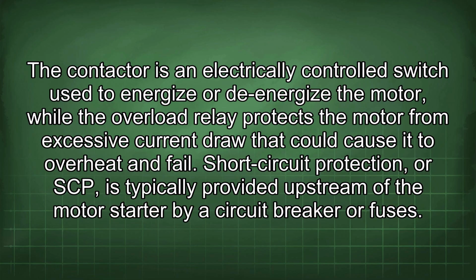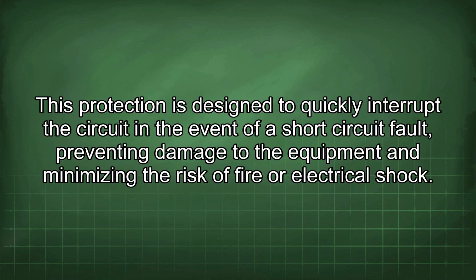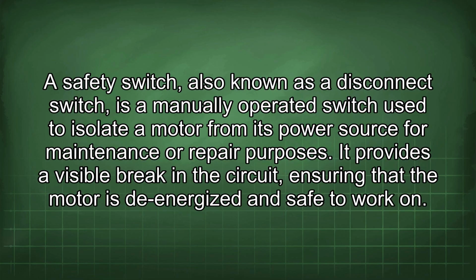Short circuit protection, or SCP, is typically provided upstream of the motor starter by a circuit breaker or fuses. This protection is designed to quickly interrupt the circuit in the event of a short circuit fault, preventing damage to the equipment and minimizing the risk of fire or electrical shock. A safety switch, also known as a disconnect switch, is a manually operated switch used to isolate a motor from its power source for maintenance or repair purposes. It provides a visible break in the circuit, ensuring that the motor is de-energized and safe to work on.